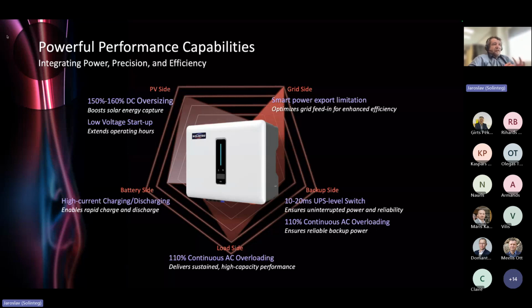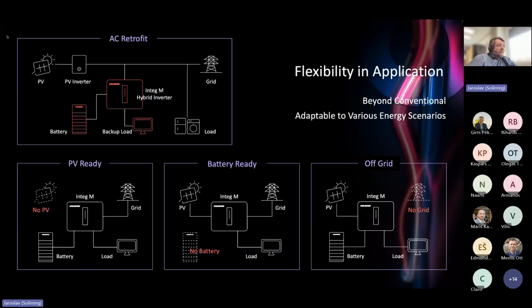On the grid side, we have smart export limitation, and on the backup side, the inverter has integrated backup output. On the backup side, we need 10 to 20 milliseconds for switching to UPS mode. 10 milliseconds is for the inverter 4 to 20 kilowatts and 20 milliseconds for the inverter 25 to 50 kilowatts. You can also overload the backup output at 110%. The same is on the AC side, on the grid side.